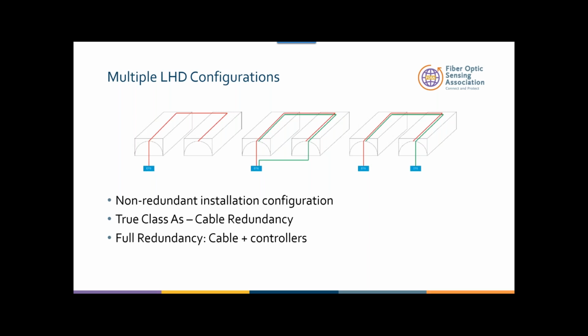So the third configuration is you get a full redundancy. Full redundancy means what? You can get 2 DTS or 2 fiber optic linear detection controllers monitoring the entire cable and 2 different cables.